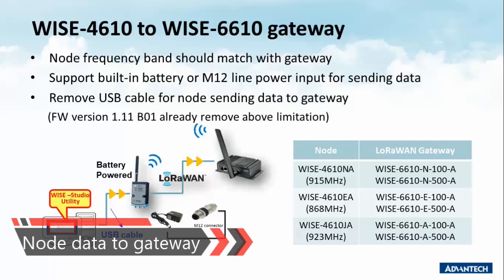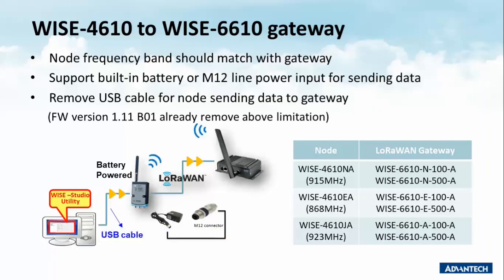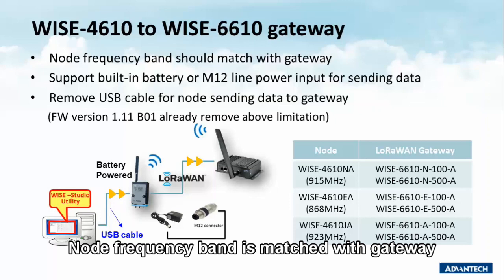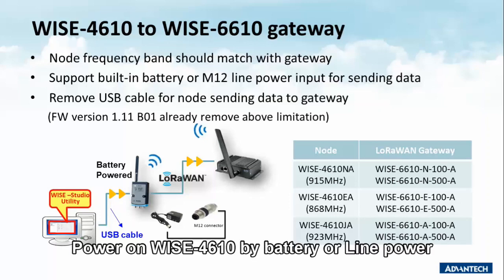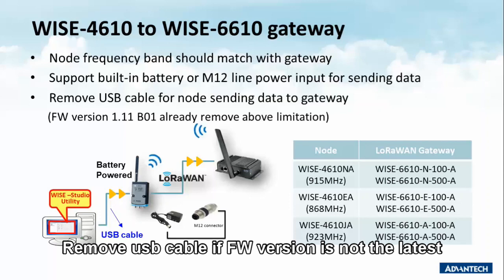Here are three important notes to make WISE-4610 successfully upload data to the WISE-6610 gateway. First, please make sure that the node frequency is matched with the gateway — you can find the corresponding gateway for each node via the table below. Second, the WISE-4610 needs to be powered on. Third, if you are using an older firmware version, you have to remove the USB cable for the node to send data to the gateway.